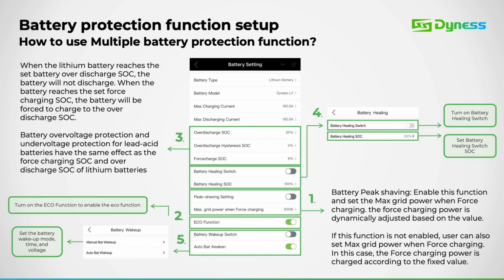Battery protection functions. Within the battery settings page, you'll find a range of functions that can be enabled as needed. Here, you can set the over-discharge SOC and force charge SOC. Over-discharge ensures the battery maintains a specified SOC percentage, preventing it from discharging further. The battery healing option is also available, allowing you to equalize a lithium battery back to 100% SOC if necessary. Additionally, the battery wake-up function can be enabled manually or set to auto wake-up mode, providing flexibility in managing the battery's operation. This includes the force charge option.